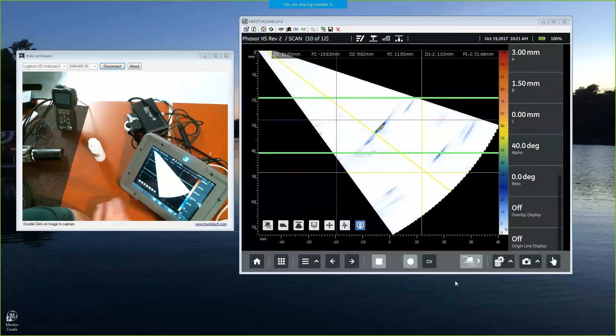So each of those tools again comes with a selection of readouts. We pop open Create here for a second. You can see, if I select the sector scan, here's where I turn on which readouts I want to see across the top of the screen. The definitions of these are covered in the manual, so I'm not going to get into a lot of detail on that. But you have a selection of beam path, projected distance, and depth distance measurements that you can do on the sector. And again, you have a choice of 1 or 2 crosshairs. So just one crosshair on is always going to be your crosshair 1. So depth, projection, all that is based on the single crosshair.